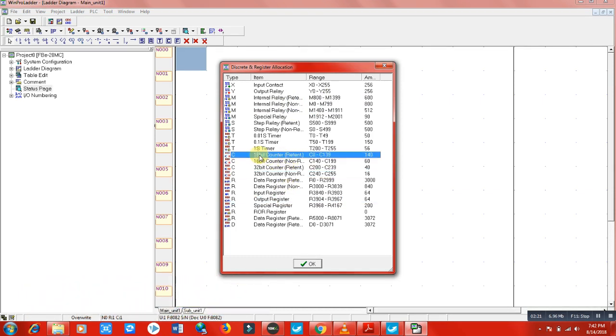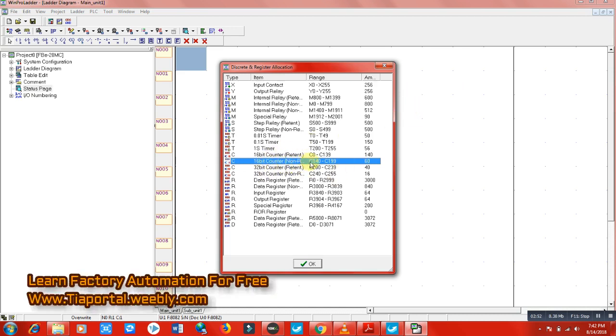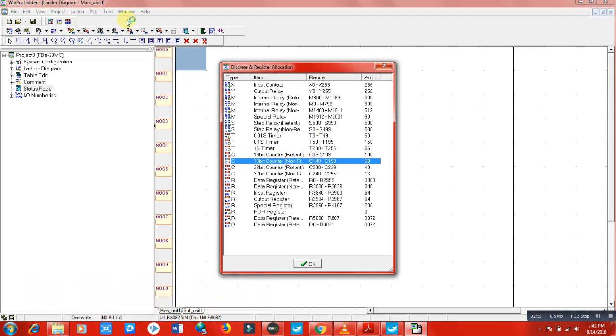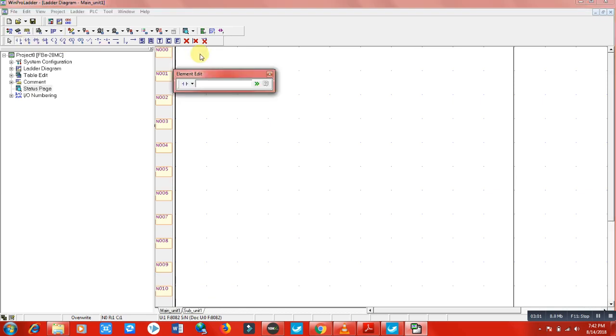Similarly, we have retentive and non-retentive counters, available in 16-bit and 32-bit. Retentive means if the current counter value is 10 and I switch off my PLC, when I switch it back on the retentive counter will start from 10 — from the same value it had before. A non-retentive counter will not remember its value and will start from zero after switching the PLC.